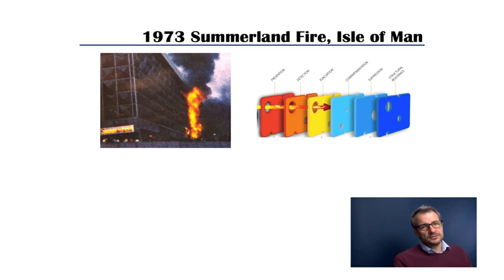Some of the evacuation routes and doors were locked because of safety concerns and security concerns, sorry. And this led to a very, very slow evacuation process, much slower than it should be. That layer of protection was breached. Compartmentation was definitely breached. It was one of the major breaches of this fire because, and this might sound familiar to you, the walls of this building were flammable.